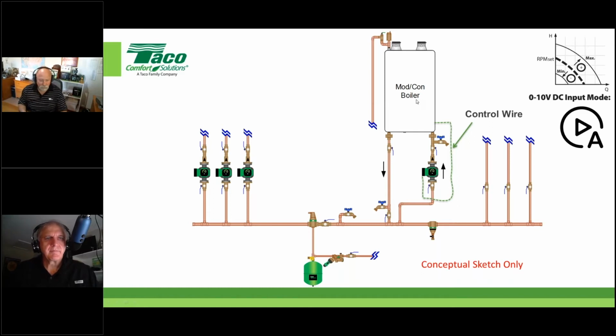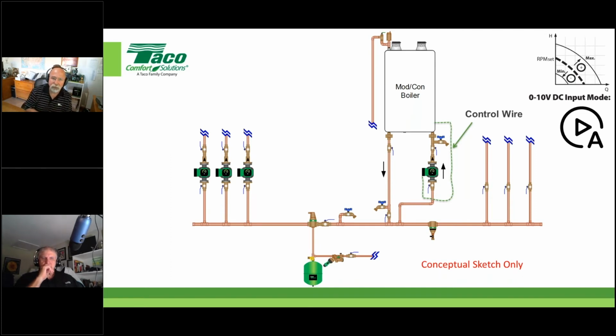Here's where the rub is. Not every boiler manufacturer has that output, and not every circulator manufacturer has the ability to receive that in circulators that are appropriately sized. It's my experience that when a circulator gives you the ability to receive that third-party signal, like 0 to 10 or pulse width modulation, normally those circulators are pretty good size, up into the intermediate size, and they tend to be bigger than the boiler actually needs to have on it. So it's kind of a rub at that point in time. Just make sure that both those things add up, that the boiler manufacturer has the output and the circulator is the right size and has the ability to receive that signal. And by all means, go ahead and do that.